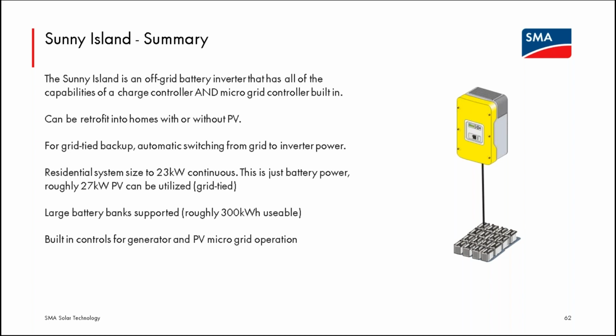Do you want to just expand on the frequency shift power control a little bit more, if you don't mind? Yeah. So again, when the Sunny Island is actively creating the microgrid, it's in control of setting voltage and frequency. And if it sees there is more, let's say, PV power on its microgrid than it needs for the loads, it sees power coming back to it. It doesn't need it to charge the batteries. It raises the AC frequency from 60 hertz upwards to get rid of that excess power. A standard, quote unquote, grid tied inverter at 60.5 hertz, above that, the grid is seen as bad, and so the inverter must stop exporting power. So the PV inverter would go from whatever it's producing to 0 watts.